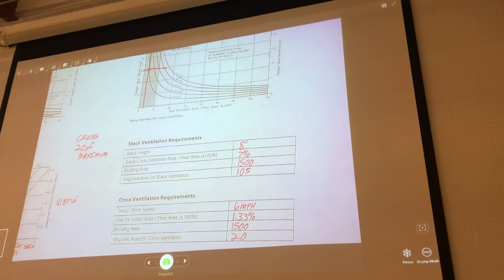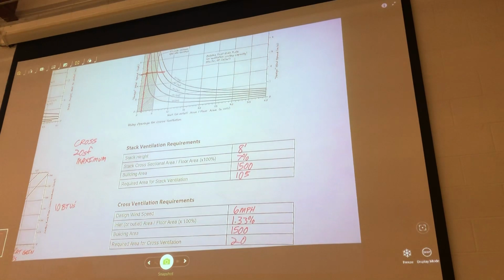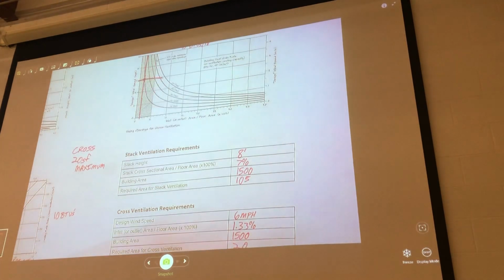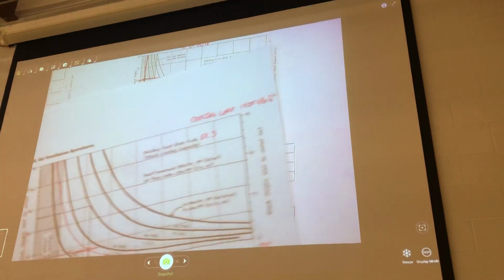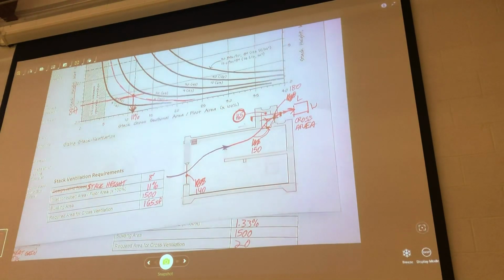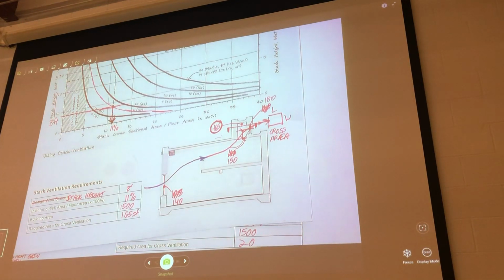Yes? So if we start with the stack first, we usually got 165 square footage, we would have to start with a smaller maximum than that. So our stack ventilation, we figured, what was it? It was 165, yeah. So just something that's smaller than the 165. So let's say you did stack and you could only do 100. That's the maximum that you could possibly design for and still make it to where it meets your aesthetics or code reasons or cost or whatever it is that you make as your limitation.